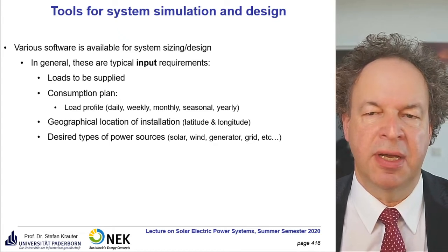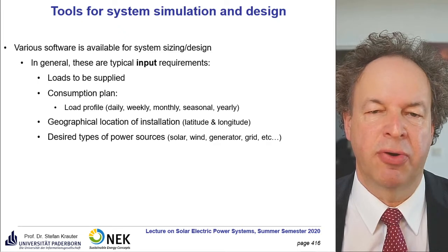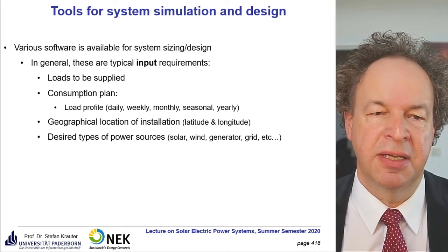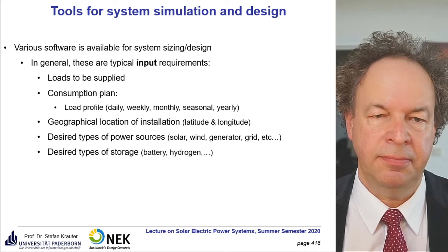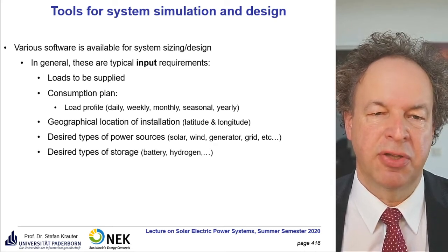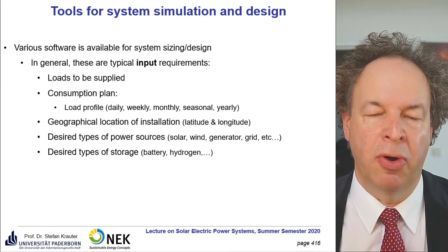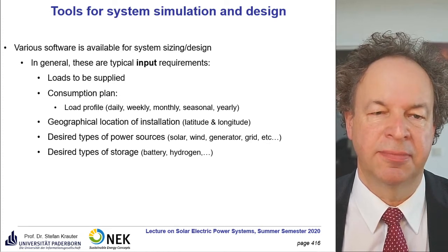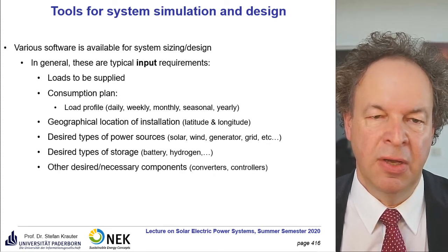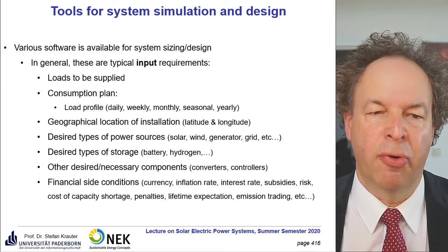You can also make different modifications: first start with a simulation without wind, for example, just using solar with or without a generator, and see whether they are feasible, then do a cost comparison. For storage, options include battery storage for smaller systems, electrolyzer and hydrogen storage for large-scale systems, or if available, pumped hydro storage. Other components include converters and controllers, and very importantly, the financial side conditions.